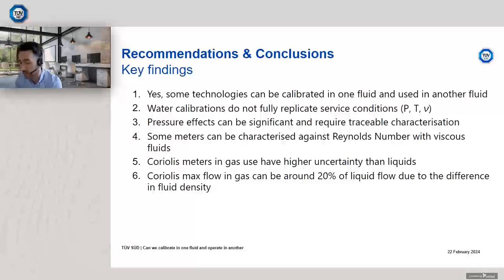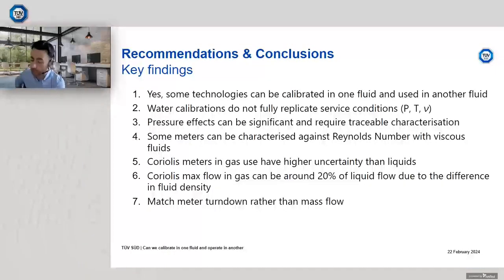What do you match? Do you match mass flow? Or do you match meter turn down? Or do you match velocity or Reynolds number? We do recommend trying to match that turn down, but also to at least try and replicate some of the mass flow as well. So match both mass flow for certain low flow rate points and then match meter turn down for the rest. And again, this isn't the optimum recommendation. The optimum recommendation is still to calibrate in the fluid or close to the same fluid. So gas for gas use, liquid for liquid use. But if you have a high uncertainty application and you're trying to use a relatively low cost calibration, there is the option of using a water calibration for gas use.